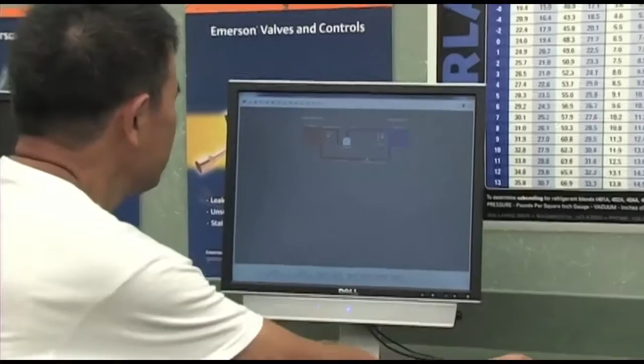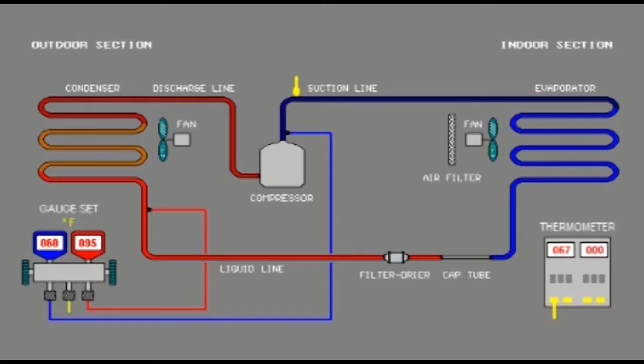Now he just installed a set of gauges. Now he's going to calculate subcooling. Now he's installed a thermometer lead on the suction line to calculate superheat. This is a very important step in the troubleshooting process when diagnosing mechanical refrigeration problems.